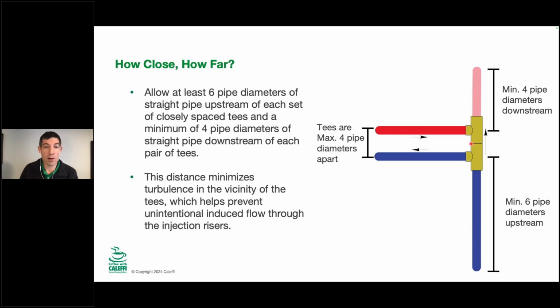So for purging a boiler, it's great to have a ball valve right here. If you put a ball valve right there, then you fill the system, you force flow through the boiler heat exchanger out through the system, and you can do the whole thing in one pass. That's helpful for that task, but it may not be primary-secondary piping anymore. And again, the test is if you put a flow meter right here or on either side of this, and you turn off the boiler circulator and you still see that you have 215 GPM of flow there, you missed something there and you've induced some flow from the primary to the secondary or vice versa.